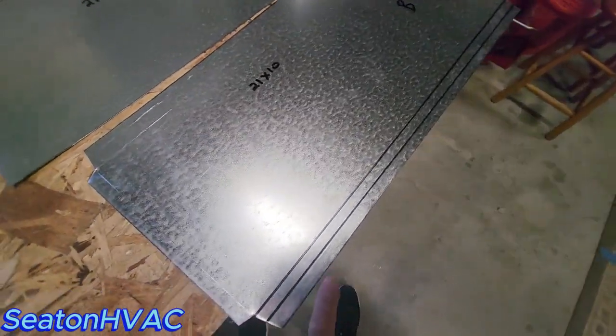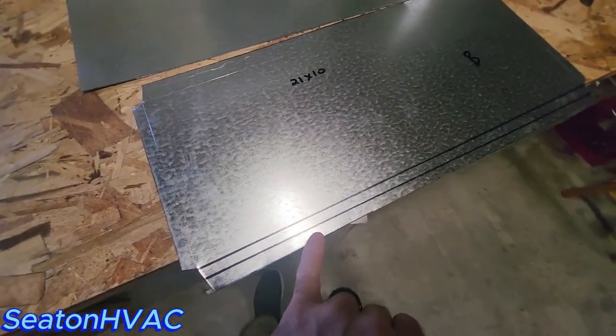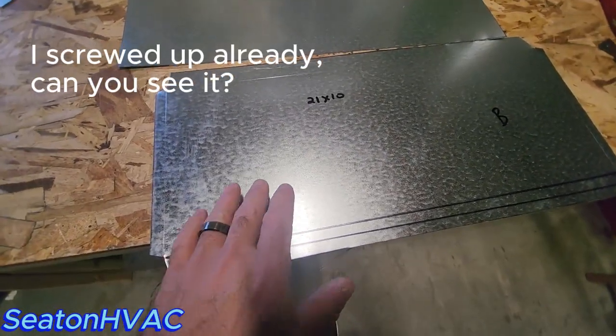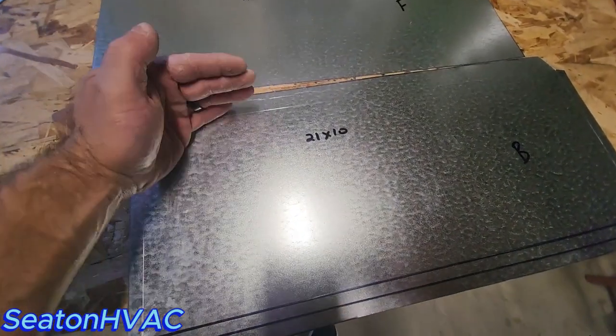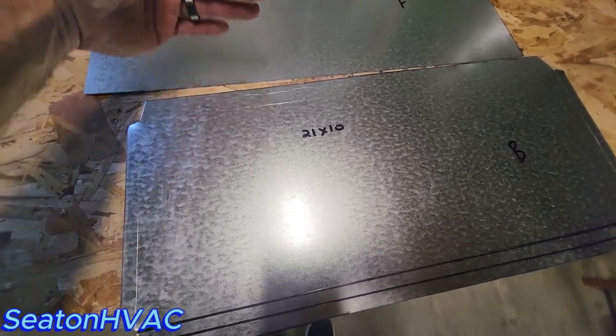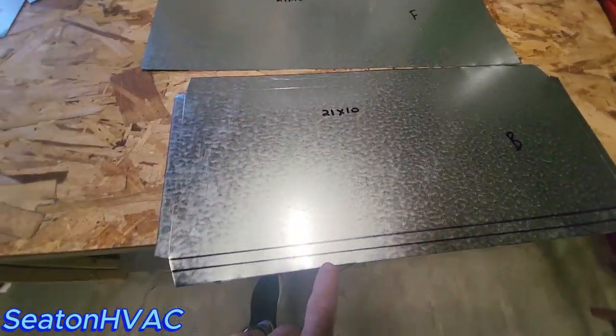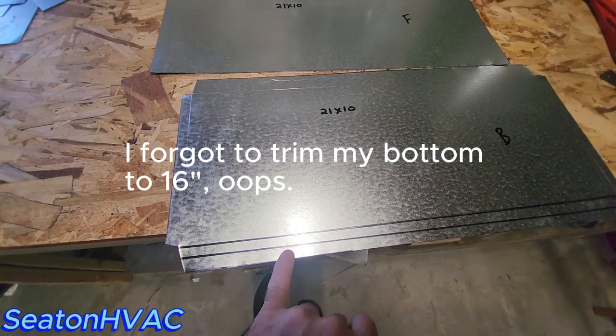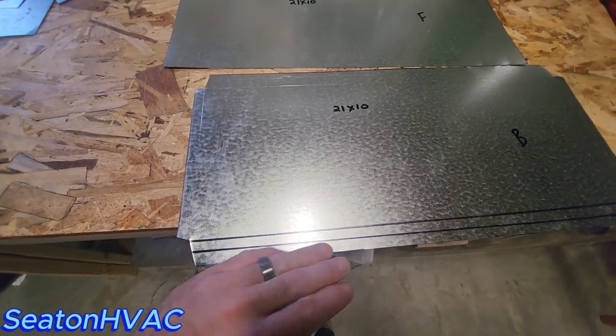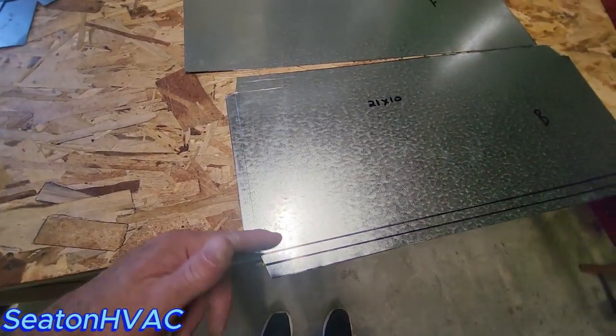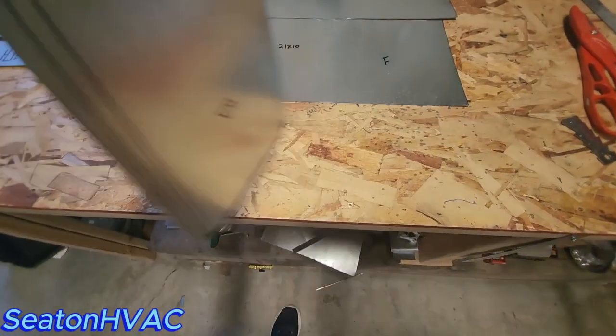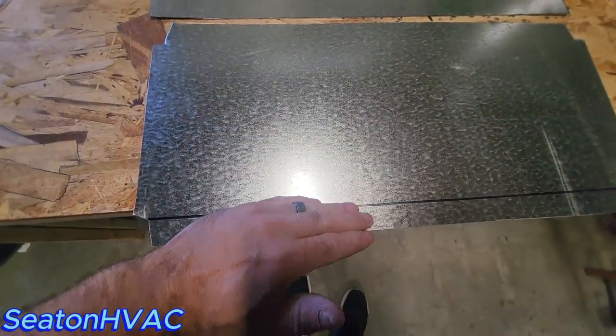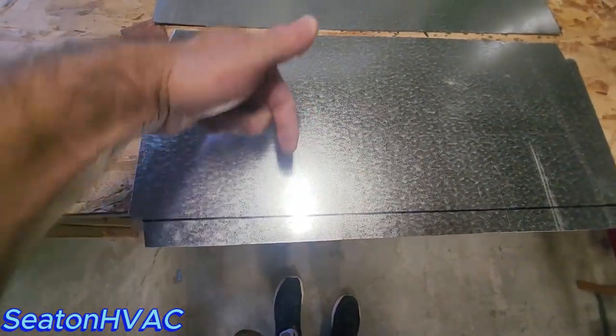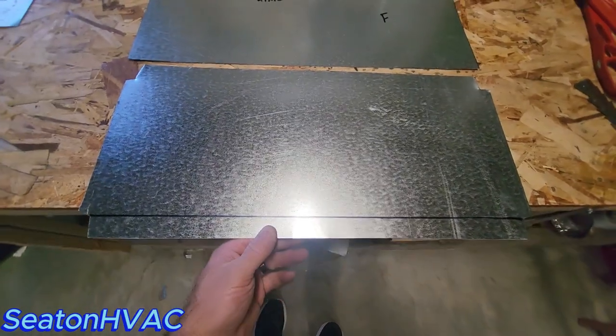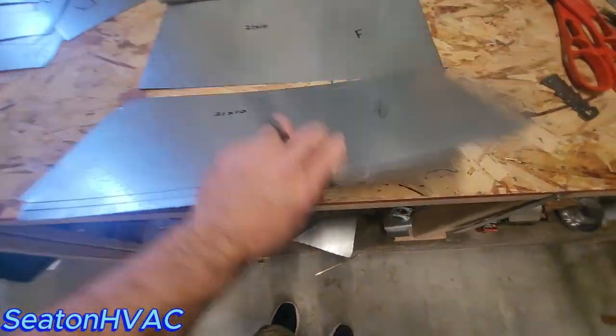Okay guys, I went ahead and marked this one for you with my marker just so I can show you what I'm doing here. Remember what I said earlier, this is our 1 inch. It's going to be a 90° to accept our air cleaner, because that's the top side. This is the bottom side. This is going to be our hem and flange. What I mean by that is, this is going to hem in a 1/2 inch. Then we're going to flip it over, and that flange will come out like this, out. That gives us something to screw it down to the air handling unit, furnace, whatever it may be.